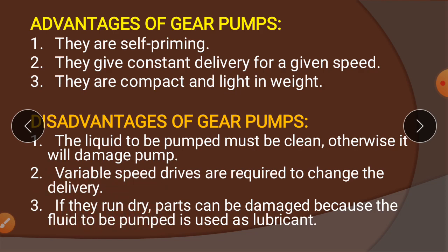If they run dry, parts can be damaged because the fluid being pumped is used as a lubricant. If the gears mesh with each other with no liquid, it will cause wear and damage the surfaces of the gear teeth. That may lead to damage of the gears. So it should have some lubricant, or else the liquid should always be present in the gear pump so that there is no damage and proper lubrication takes place.